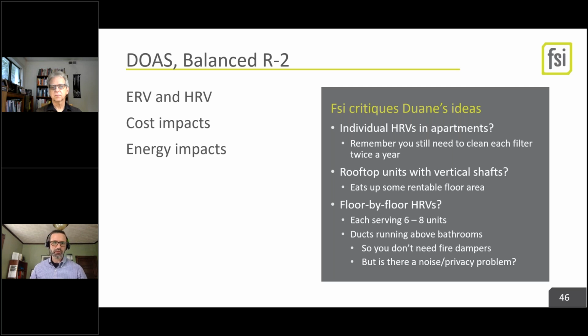So Duane asked a couple questions. Individual HRVs, heat recovery ventilators in apartments. Our critique of that, or reminder about that, is, hey, you gotta change these filters at least every 6 months. They're teeny little filter media that get clogged really easily. If you go to the large units with vertical shafts, yes, but you've got those same things about fire dampers and the floor area that you're taking up. And then doing floor by floor might be the sweet spot, because you don't necessarily need fire dampers depending on how you run it. And you certainly don't need the floor-to-floor fire dampers, but you're sharing a system that can transmit noise. So you got to be aware, unit to unit, and do some noise baffling.